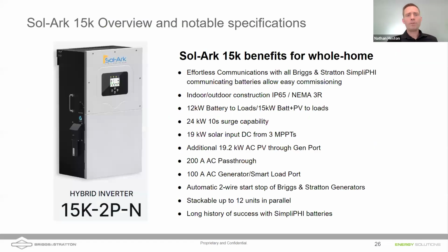But with the Sol-Ark 15k, there are a number of things that set it apart. It has effortless communications with all of our Briggs & Stratton SimpliPhi batteries, which allows for very easy commissioning. It's indoor-outdoor rated. All of the components on this unit, the hinges and the bolts, are high quality stainless steel. It's an IP65 rated NEMA 3R inverter.